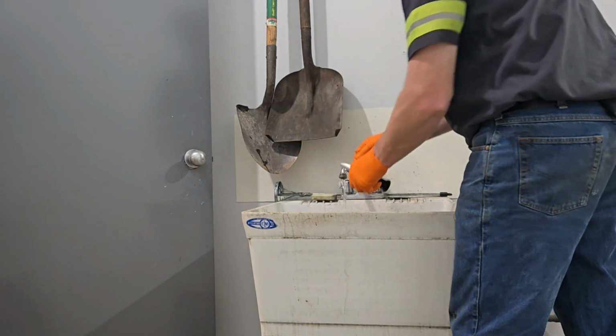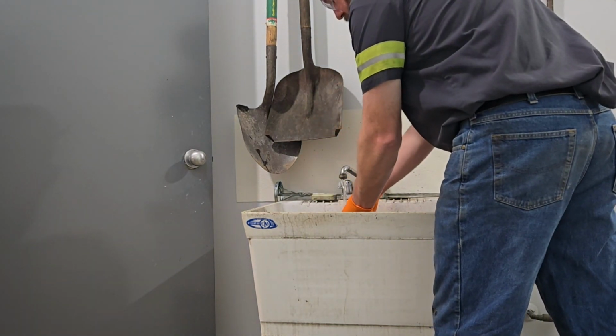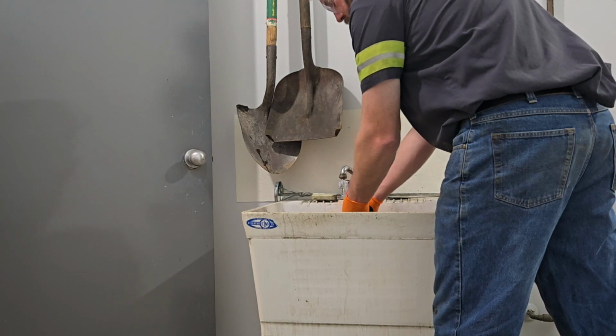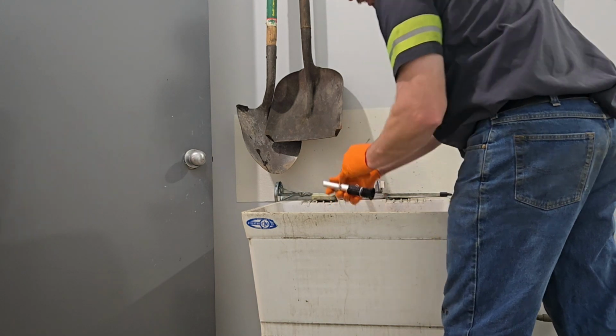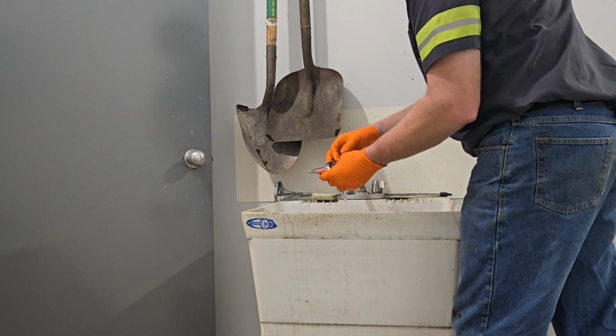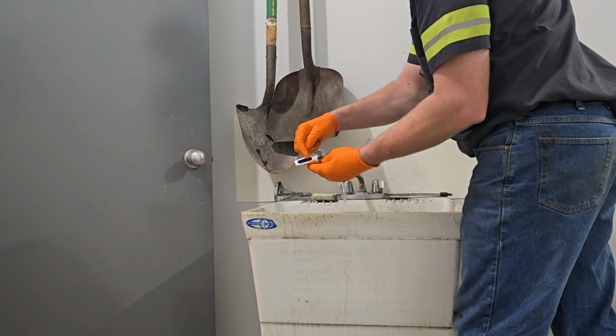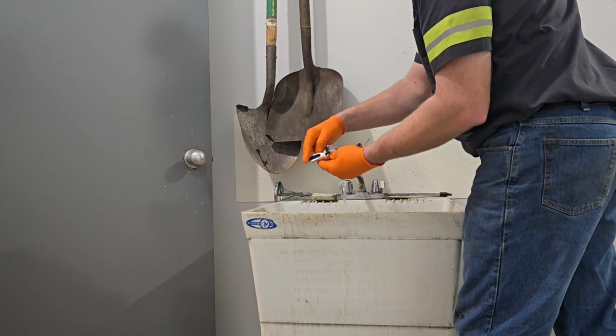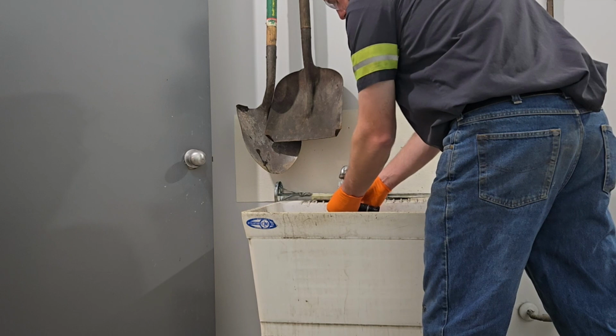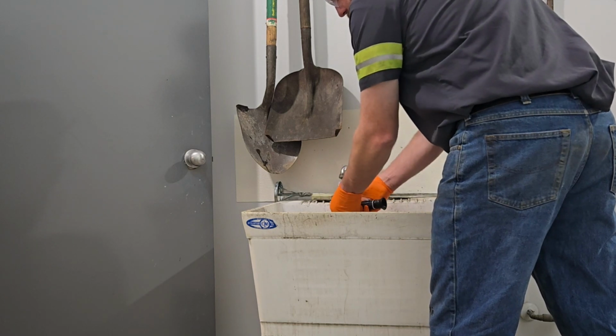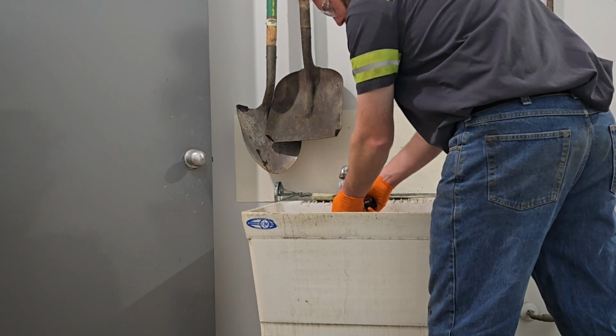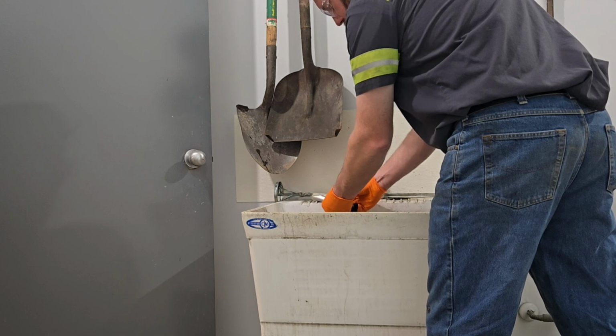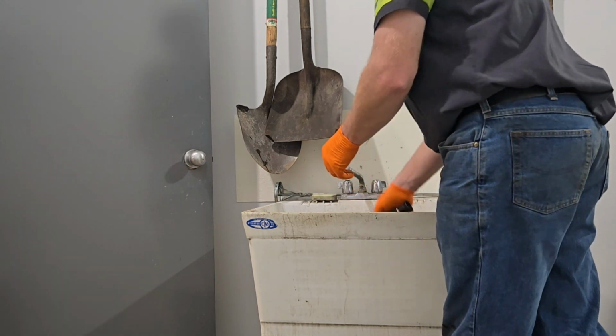The tool I wash off itself, because if you leave that acid on here, it will not only corrode the body of this thing, but actually kills the seal for the refractometer's face, and it becomes open to the elements and water gets behind the gasket. So I just make sure I wash it all off real good.